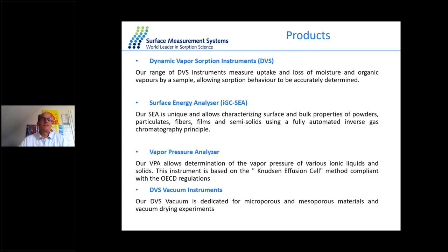As I said, the surface energy analyzer is based on inverse gas chromatography. It allows you the characterization of surface properties. We'll see which ones, but also some bulk properties of powders and solid materials. It can also be films.